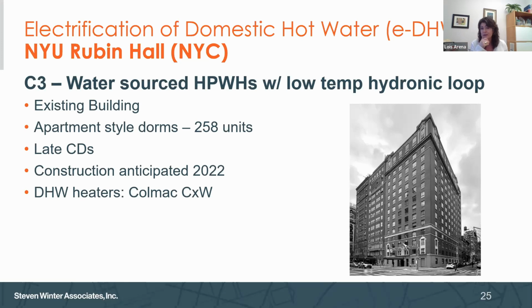And then electrical capacity: do we have enough electrical capacity to the building, and enough to the roof to run the heat pumps, the pumps, any extra pumps that need to be up there? When you look at this tall, kind of thin building, we're trying to put in heat pumps for heating and cooling, an ERV to handle the ventilation, because they're designing it to EnerPHit, and then the domestic hot water. So it is tight up there, and it's historic, so you can't see any of this stuff from the ground. You're battling all angles on that project, and they're really doing a great job trying to figure it all out. That's fantastic.